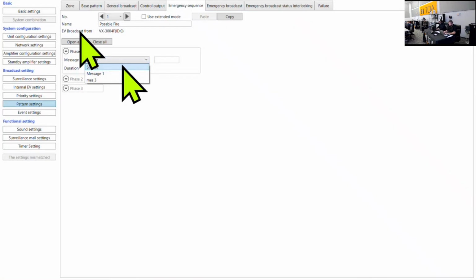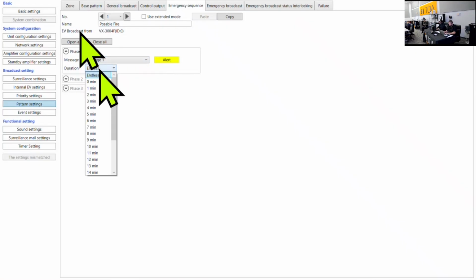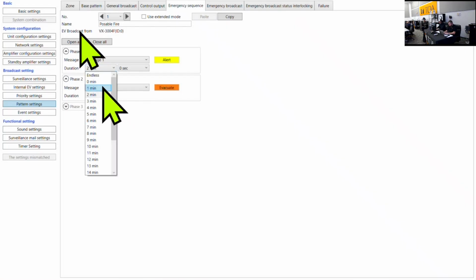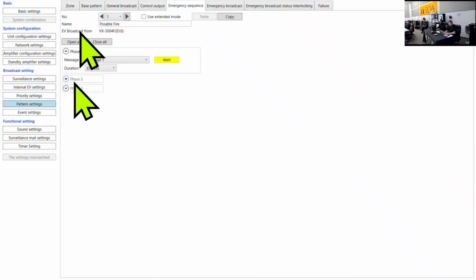For this, maybe I want to play my message 1. That's alert, and have it at 2 minutes. In phase 2, I could have it play maybe my message 3, and that could be endless. One thing to note is if you set phase 1 to endless, you can't have another phase past that.